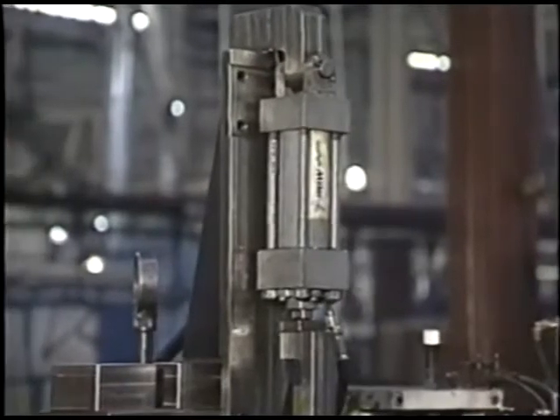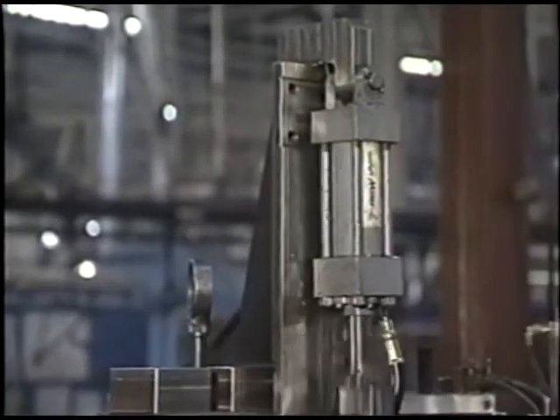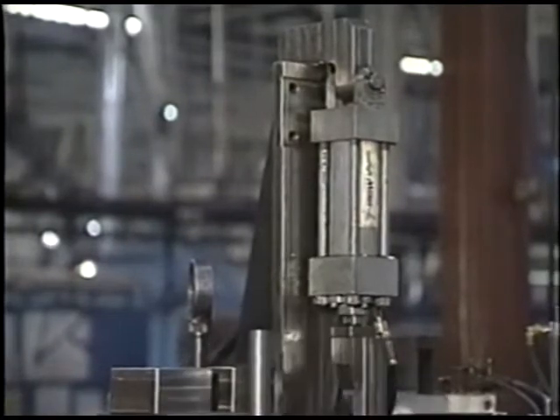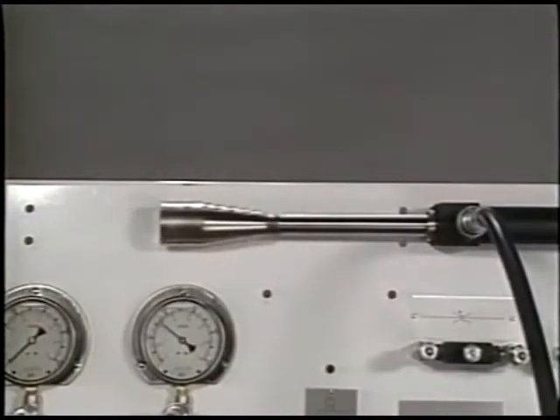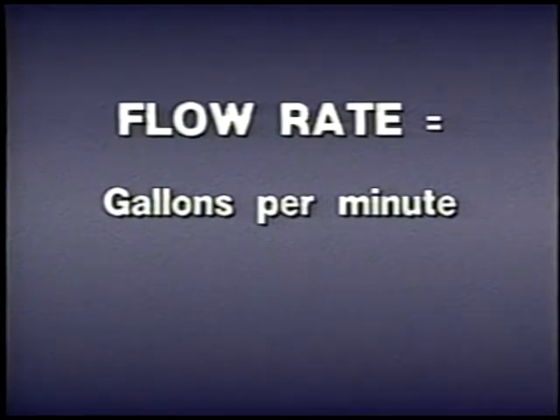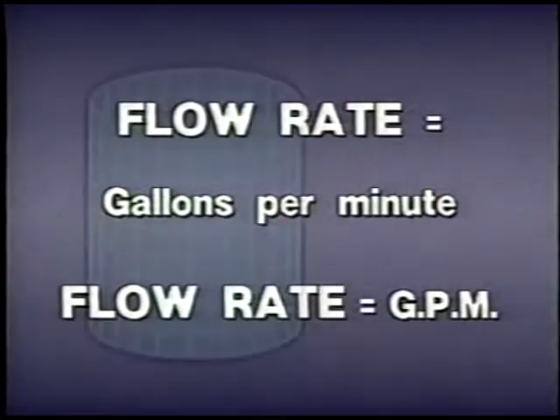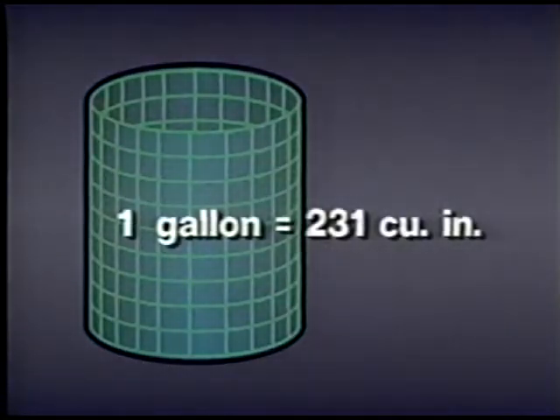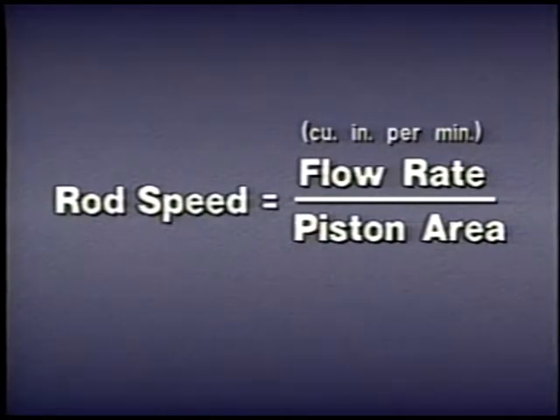The speed changes depending on how fast the cylinder fills up with fluid. If it fills up slowly, the rod moves slowly; if it fills up quickly, the rod moves quickly. How fast it fills up is called the flow rate, often measured in gallons per minute. Sometimes the flow rate is given in cubic inches per minute. You can convert to gallons per minute by dividing by 231 — the number of cubic inches in a gallon. The speed of the piston rod can be calculated by dividing the flow rate in cubic inches per minute by the area of the piston in square inches.